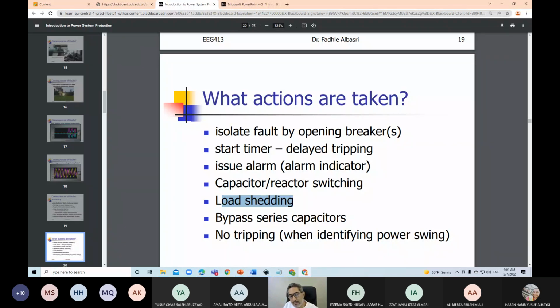Sometimes we don't take any action, although we know there's an abnormal condition, and this happens when we detect a power swing situation. A power swing is when you have a sudden loss of generation or sudden loss of load, and the synchronous machines will oscillate with each other, and create a power swing that looks like a fault from the relay perspective, but this is not a fault. This oscillation will decay with time, but the relay should identify this as a power swing, not as a fault or a short circuit.